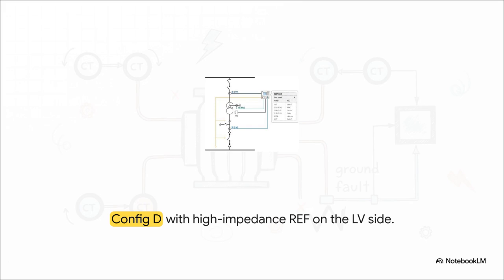To ground this abstract concept in reality, let's look at a physical setup. Here we have the RET615 applied to a 2-winding power transformer in standard configuration D. Notice the high impedance REF protection applied specifically to the low voltage side. The CTs on the phases and the CT on the neutral must have perfectly matched ratios for this particular physical setup to accurately monitor the protected zone without false tripping.